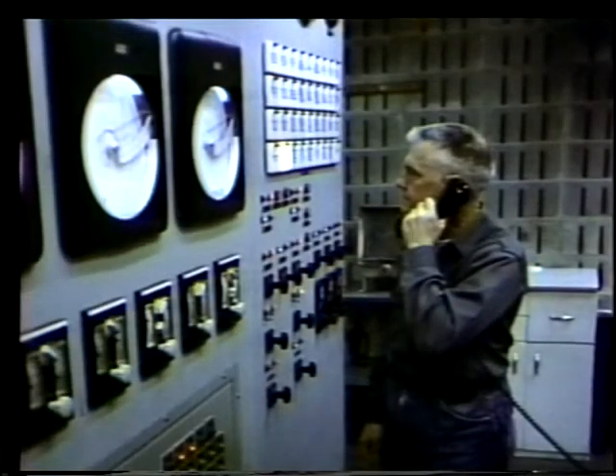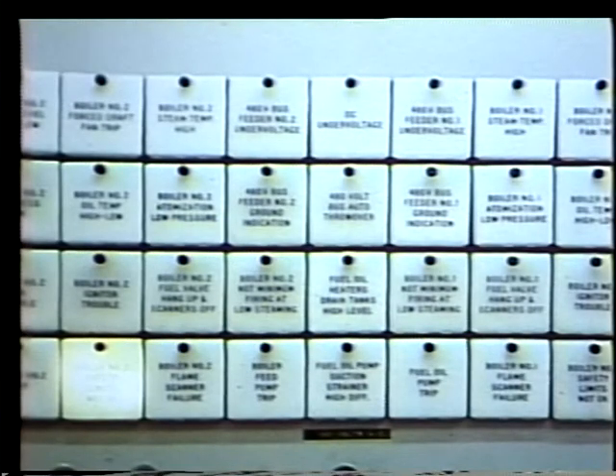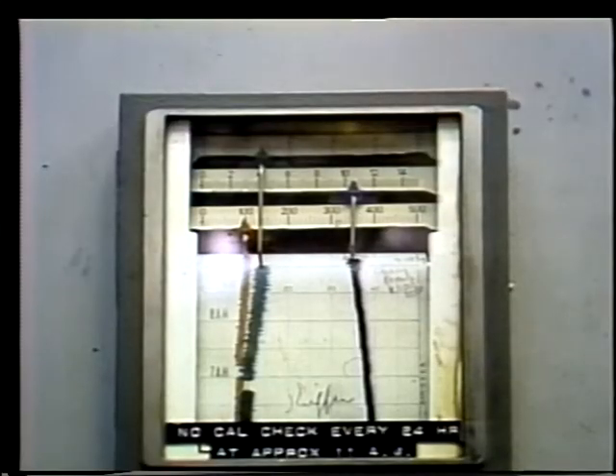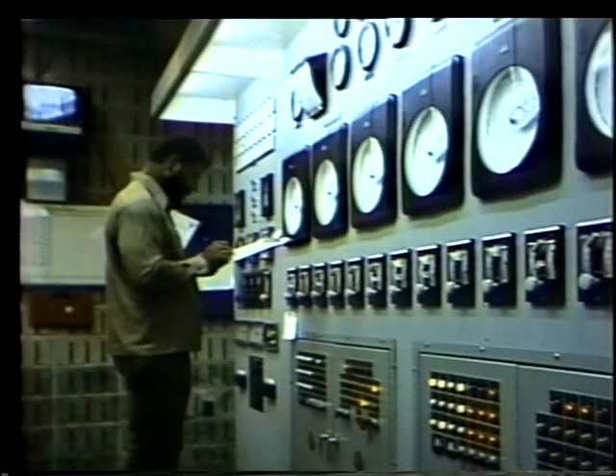In the control room, the operators have gauges which give a constant readout of plant functions. They've got telltales to call their attention to anything they might have overlooked, and alarms which tell them if a part of the system is starting to seriously malfunction. The operators are always monitoring plant efficiency by taking figures from a number of gauges and recorders and comparing the figures they get with a practical ideal figure. If efficiency in the system as a whole or a part of the system falls rapidly or falls steadily, it's a clue to them to look more closely to pinpoint where the problem may lie. For example, if the temperature of the condensate from the main condenser is too high and at the same time the cooling water temperature coming out of the condenser is low, it means that deposits are probably affecting efficient heat transfer in the condenser, which could lead to inefficient turbine operation due to low vacuum.